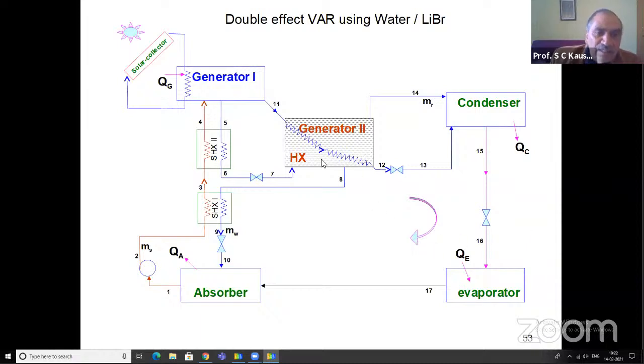But at the same time, the operating pressure in generator 1 is excessively high. So we cannot use ammonia water as a working fluid for a double effect system. Only water lithium bromide can be used for the double effect vapor absorption system, where operating pressures are much lower than atmospheric pressure. So we don't need high pressure vessels.